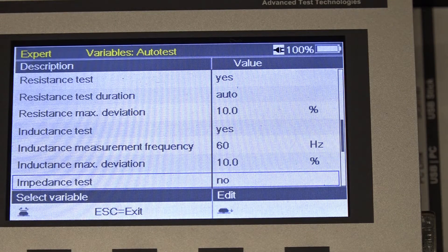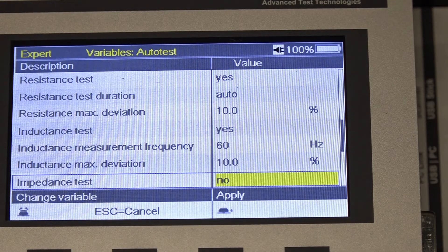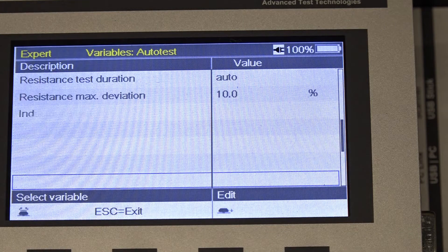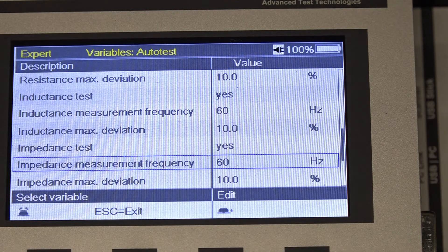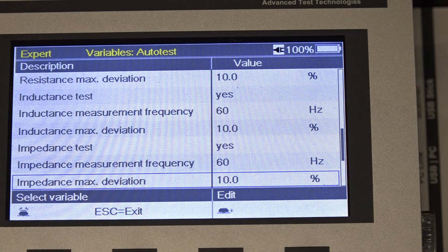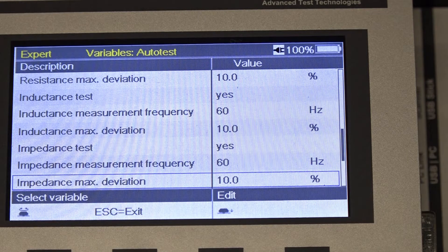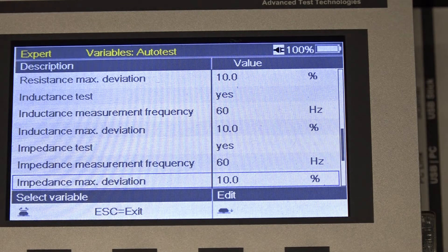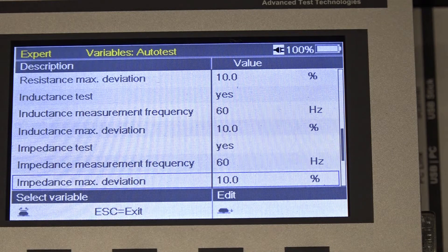Let's also turn on the impedance test. Got it turned on. And again, we'll do it at 60 hertz and accept 10% for the maximum deviation. Now, if your organization would like to change this, or you want to change the frequencies for these tests, that's fine too.